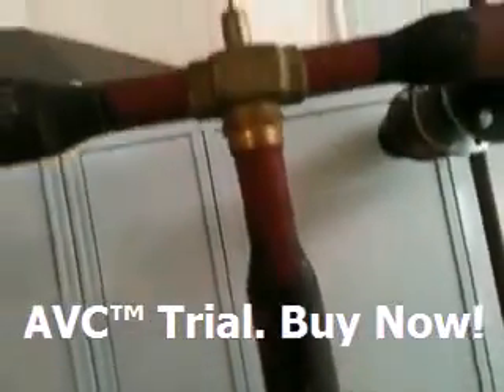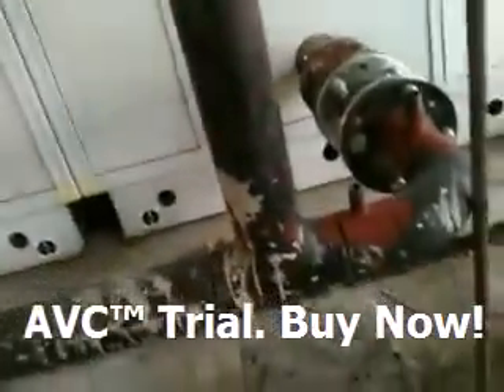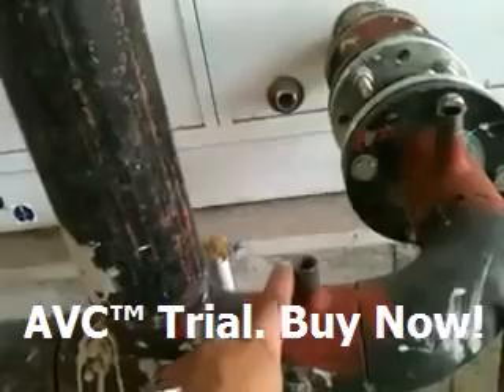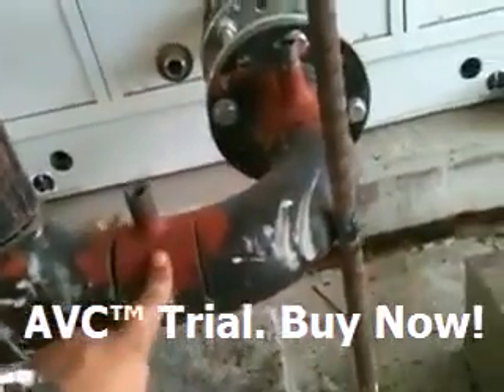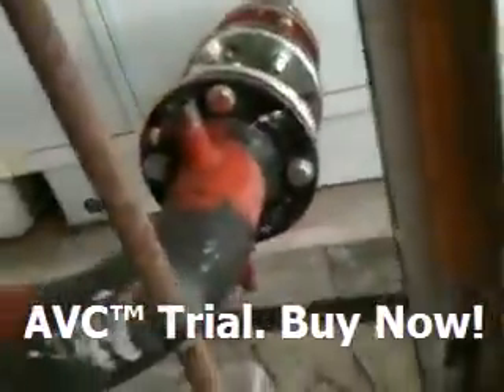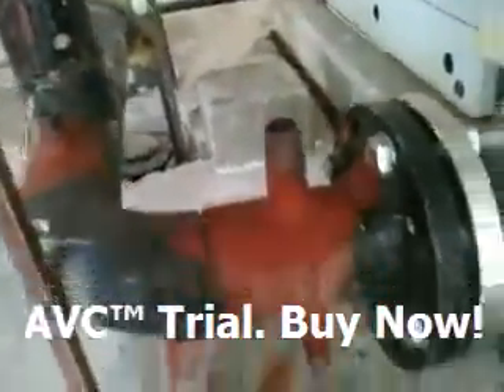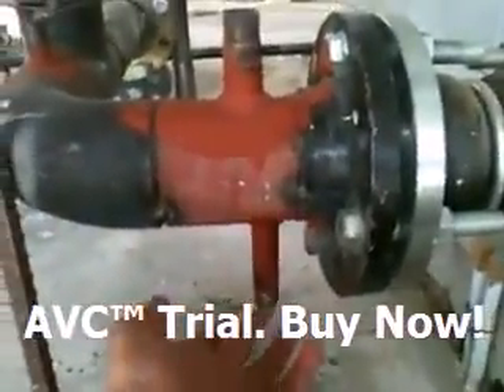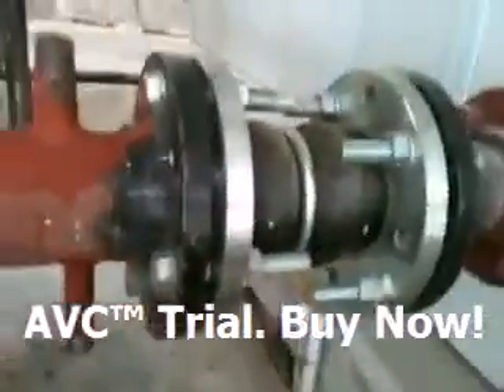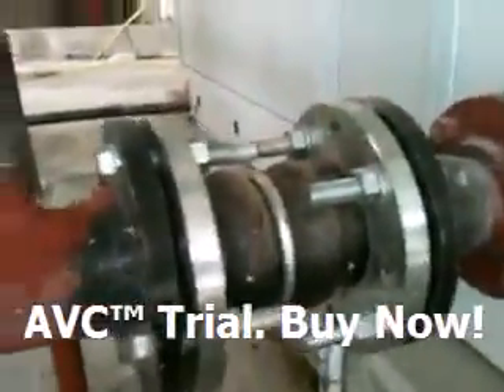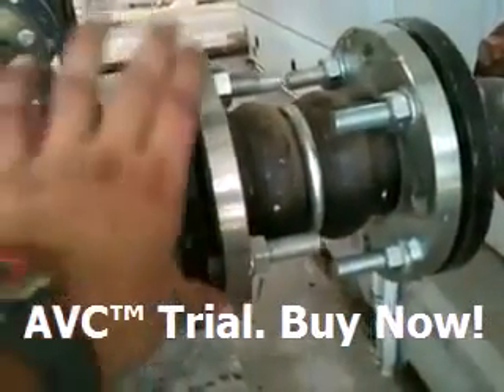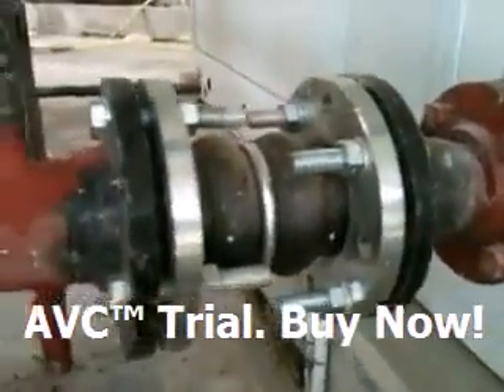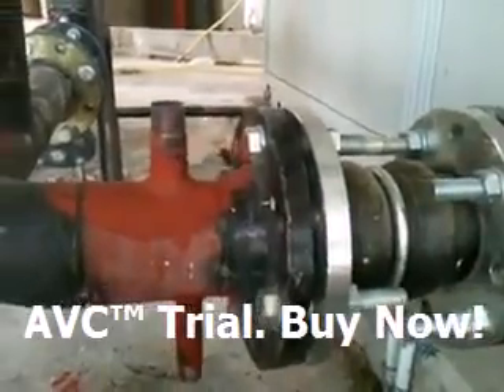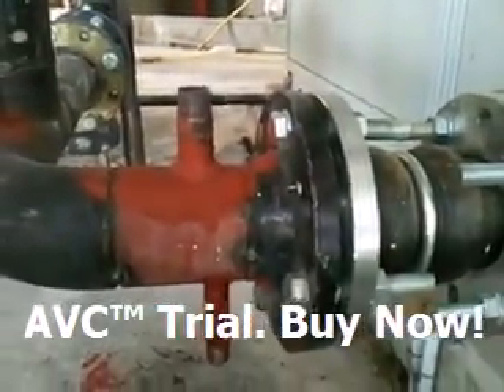we are having this one, the bypass from the chilled water return. This is the bypass, and here this is the tapping for pressure gauge, quarter inch size, 1/4 inches for pressure gauge. Now if you see, we are putting one elbow, and then we have this tapping for thermometer, and this tapping is of 3/4 inches, and this one of 1/4 inch. This is for drain. Now we are putting here a flexible, of the same size, 3 inches DN80, and this also has a flange connection. Okay, normally we have flange connection for pipe size of more than or equal to 3 inches.